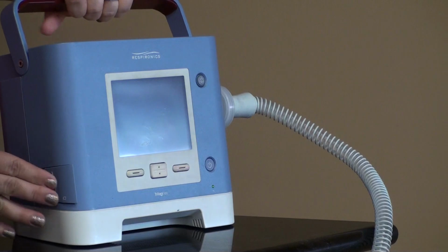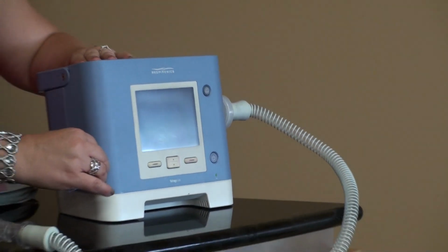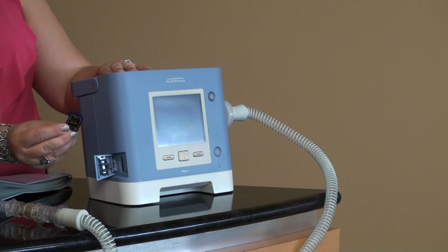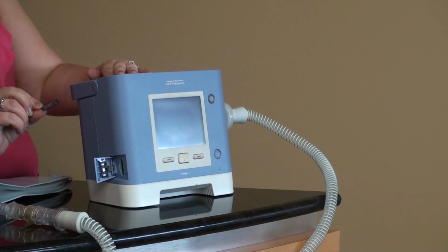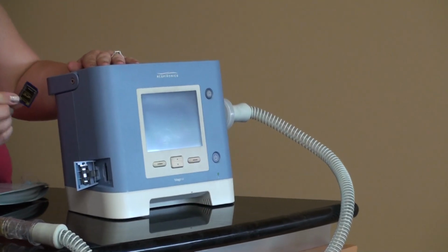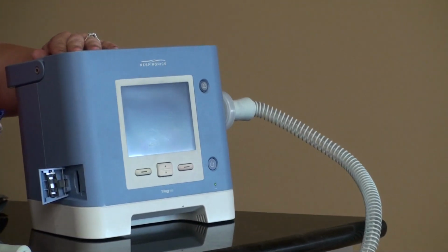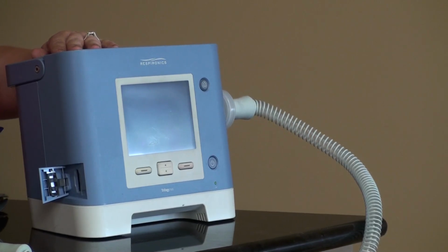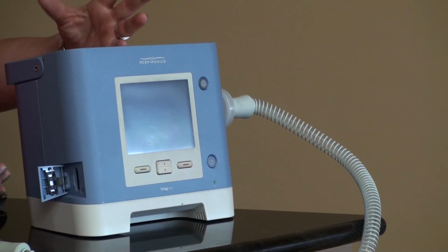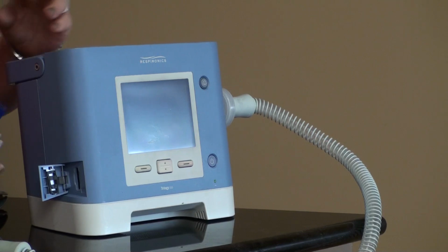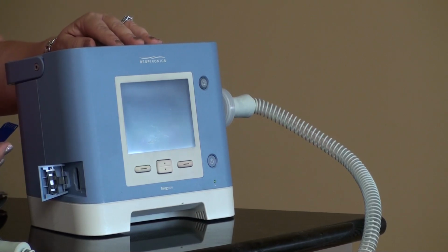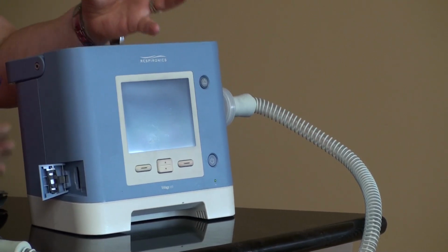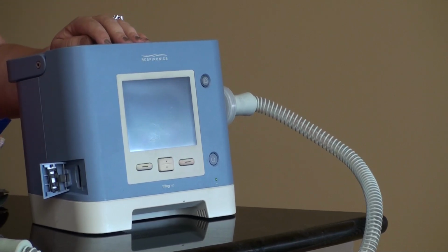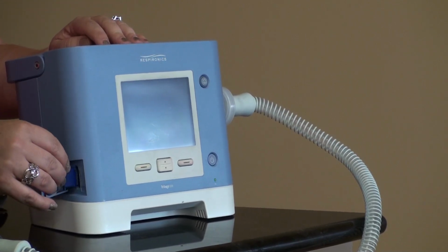Okay. Then on this side of the ventilator, you have what they call an SD card. It looks just like a camera card, just like for your pictures. It's a 1 or 2 gigabyte memory, and it records 72 hours of raw data, so breath by breath. It compacts that into daily details for the past 30 days, and then it compacts that into trends overviews of the last 12 months. So it basically has a year's worth of ventilation data in it.